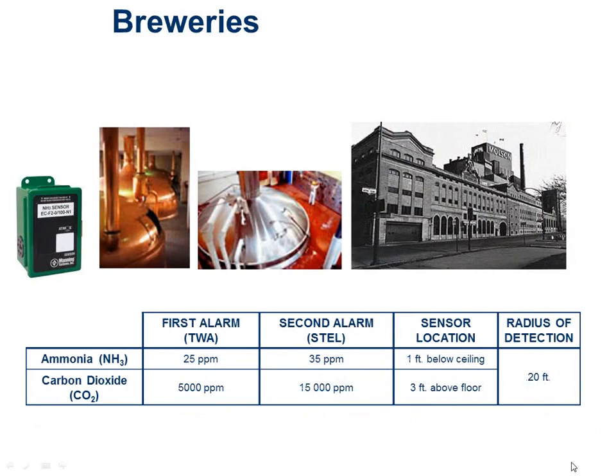Ammonia is NH3. Whether it's a brewery or an ammonia chiller in an ice rink or whatever, my threshold is 25 parts per million that I want to control to. That means my exhaust fans kick on, and I try to keep it below 25 parts per million. I still notify the BAS if I have one. If I get to 35 parts per million, that's when the strobes and horns go off. Ammonia is typically lighter than air, so I will measure it up at the ceiling, and I get about a 20-foot radius of detection.